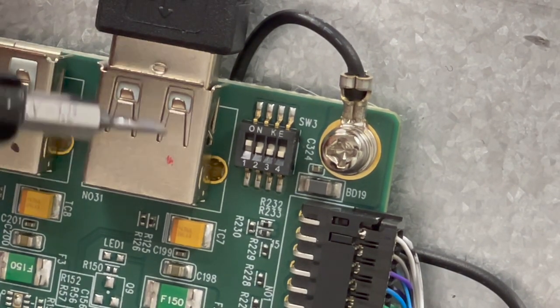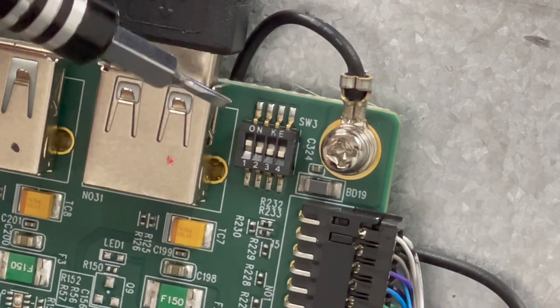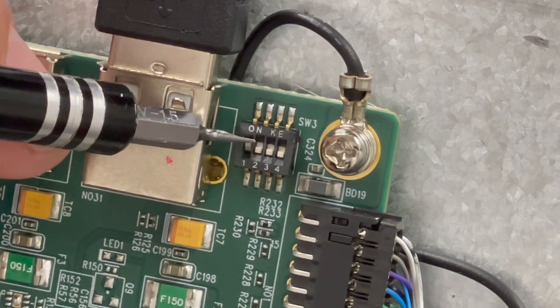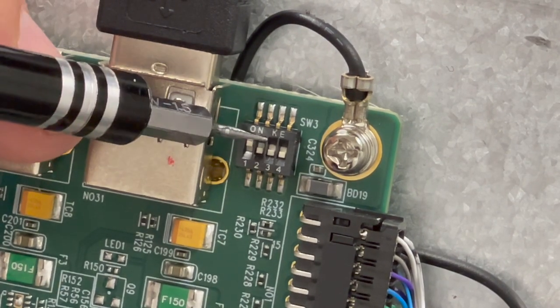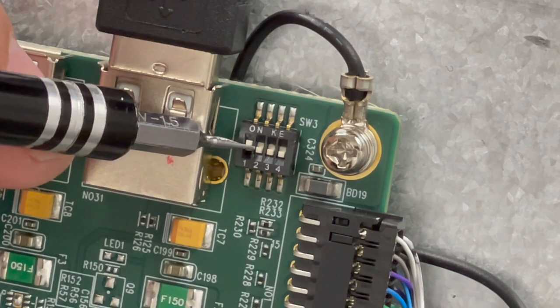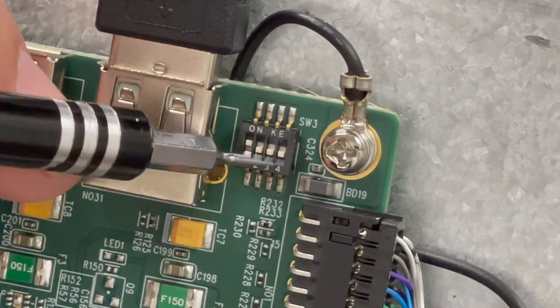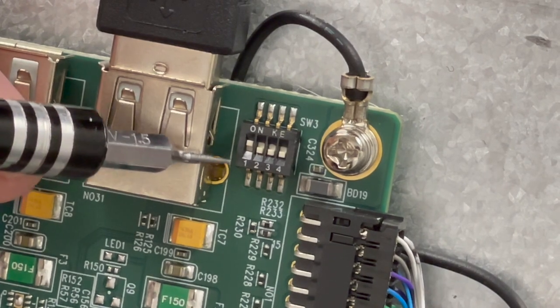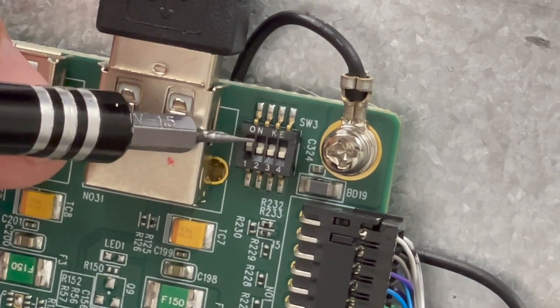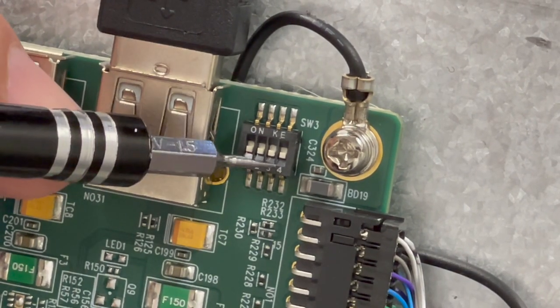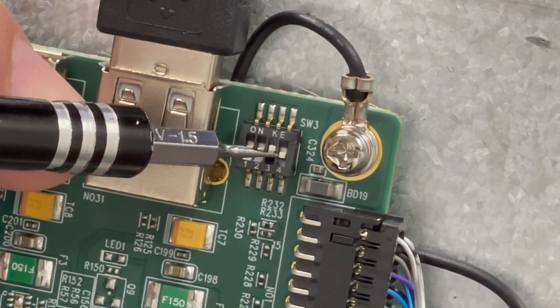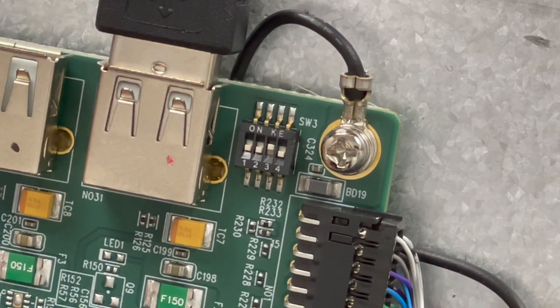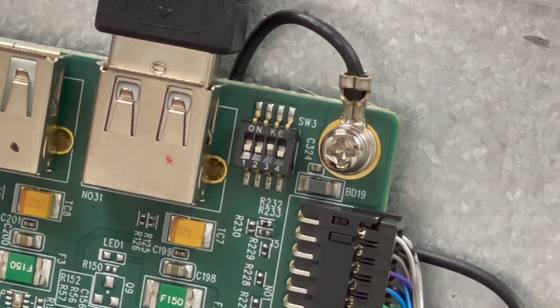I'm using a fine tip screwdriver here and what I'm going to do to move the switches is, here switch number one is up and two, three, and four are down, which is wrong for this model. And I'm going to push switch one back down and then I'm going to lift switch three up, which is correct for an ONIX.